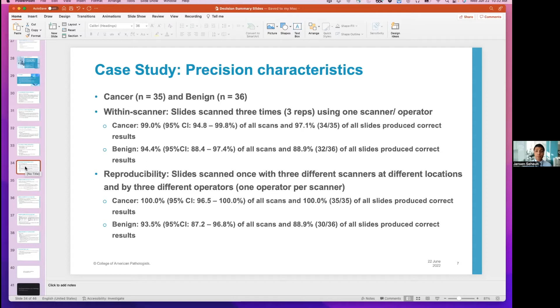I'm not going to go into the details of this, but how you might come up with the sample size for your local laboratory verification can use a very straightforward power-based sample size calculation. And I'm going to focus on the 3rd bullet point. For example, if the lab wishes to compare the locally determined accuracy of a software to the manufacturer's claim of 94.2%, the sample size required to have 95% confidence and 80% power to detect a difference of 5% lower than a claimed accuracy of 94.2% would be a sample size of 166. Excuse me. Next slide.